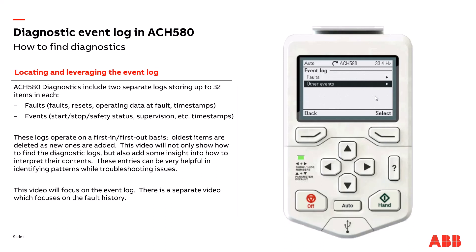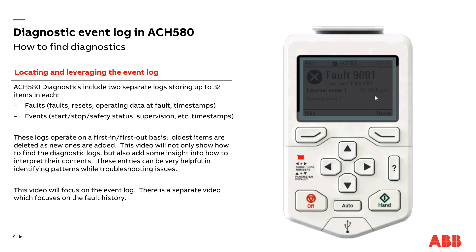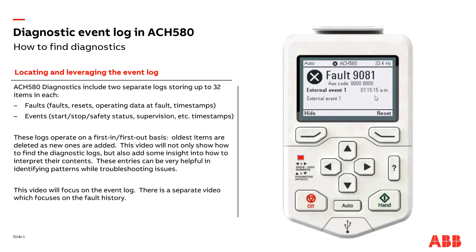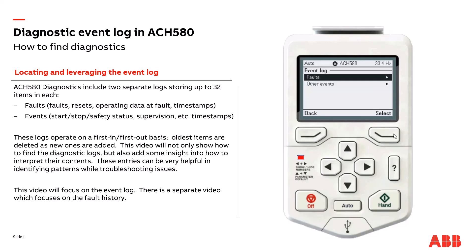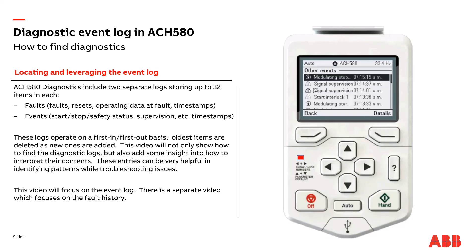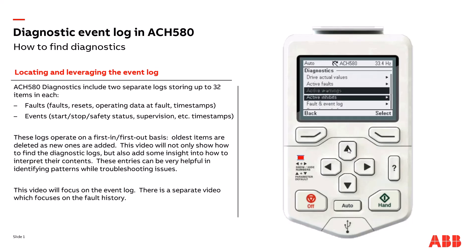I've also got the drive set up to fault, triggered by one of the digital inputs, so let's generate a fault. We see that we've got a fault now. Let's check out the fault log — we've got an entry in the fault log with its corresponding timestamp. And as I mentioned, we can use both logs together: the same timestamp shows modulation stopped due to the fault.